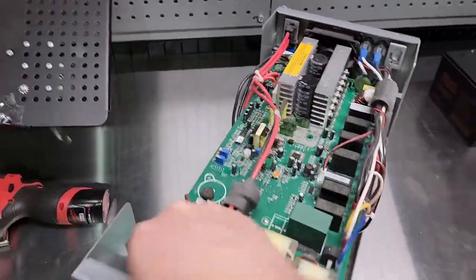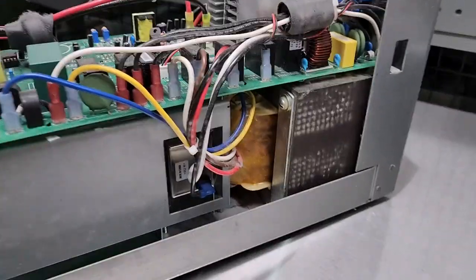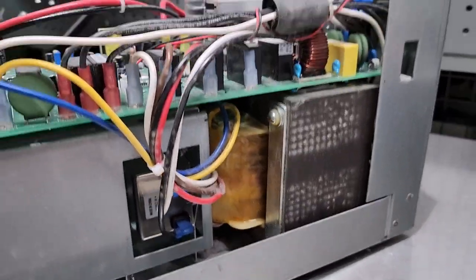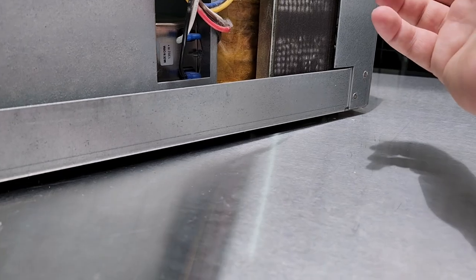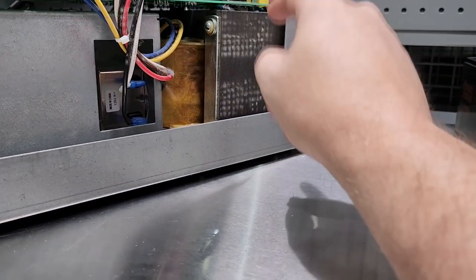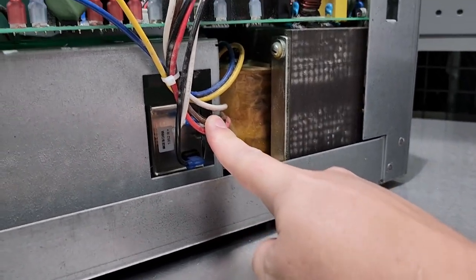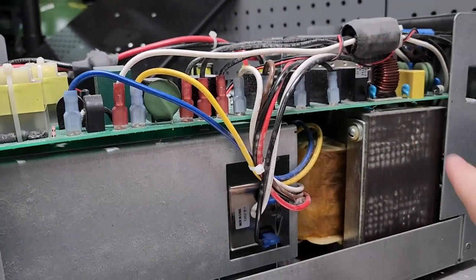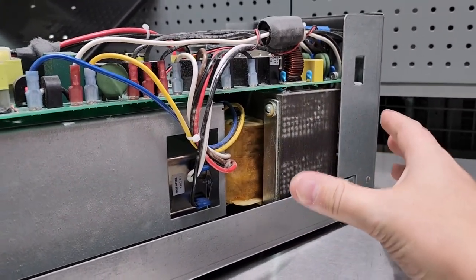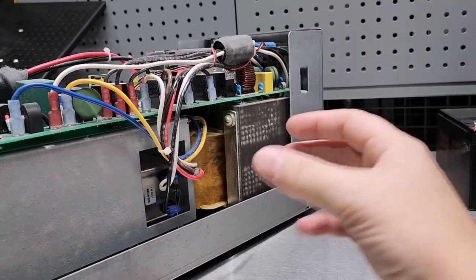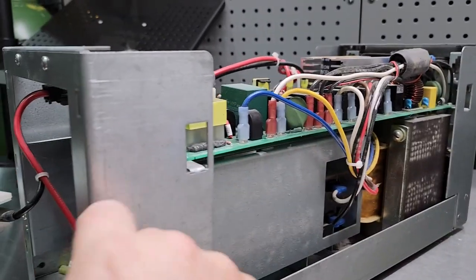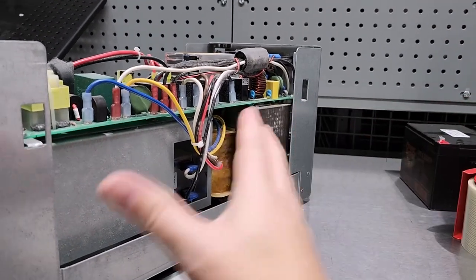First thing that you can see is this guy is ungodly heavy. It has a massive transformer down here. This transformer acts as probably a step down and at the same time an isolation. It's probably mainly an isolation transformer. You can see there's multiple taps right here, so there's definitely different voltages coming off the transformer. By it isolating, that means that whatever is plugged into this guy is also going to be a wee bit safer. UPS systems are also good at isolating wall mains from whatever is plugged in.